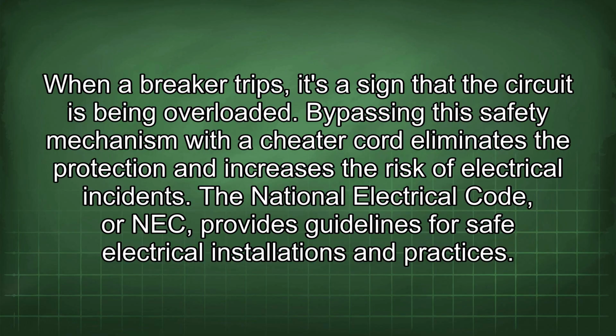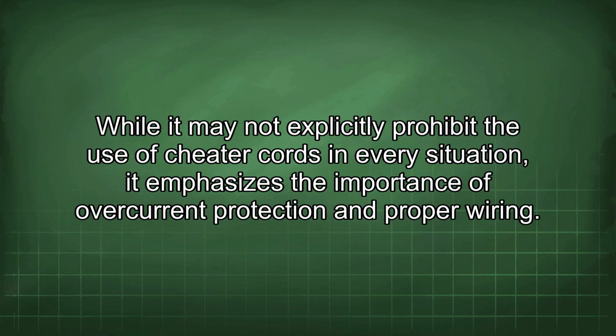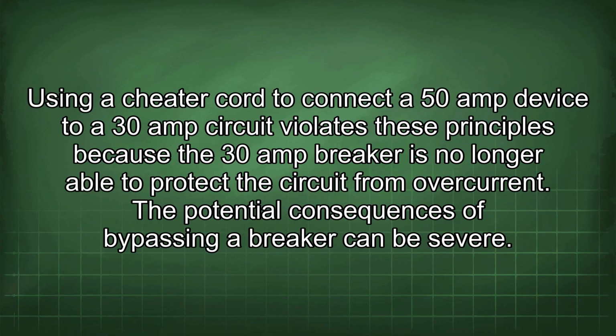The National Electrical Code, or NEC, provides guidelines for safe electrical installations and practices. While it may not explicitly prohibit the use of cheater cords in every situation, it emphasizes the importance of overcurrent protection and proper wiring. Using a cheater cord to connect a 50-amp device to a 30-amp circuit violates these principles because the 30-amp breaker is no longer able to protect the circuit from overcurrent.